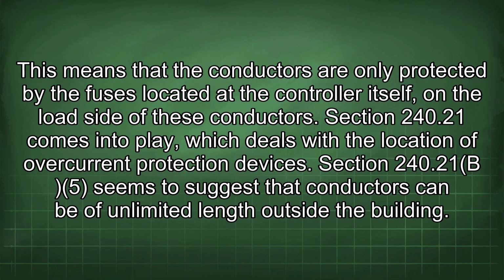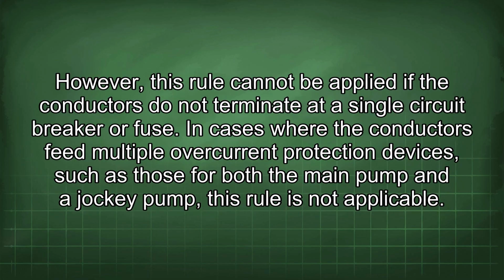Section 240.21 comes into play, which deals with the location of overcurrent protection devices. Section 240.21(B)(5) seems to suggest that conductors can be of unlimited length outside the building. However, this rule cannot be applied if the conductors do not terminate at a single circuit breaker or fuse. In cases where the conductors feed multiple overcurrent protection devices, such as those for both the main pump and a jockey pump, this rule is not applicable.